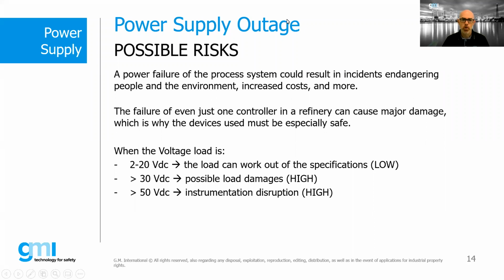Often we try to avoid this issue using redundancy, but we mistakenly think that two power supplies in parallel are sufficient to make us immune to possible faults in the power supply system. Redundancy cannot solve this on its own and cannot guarantee us immunity from power supply failure, because a standard power supply system does not take into account the common mode faults that can afflict standard power supplies. These common mode faults can cause spurious system faults with the related production downtime, and this would significantly affect cost.